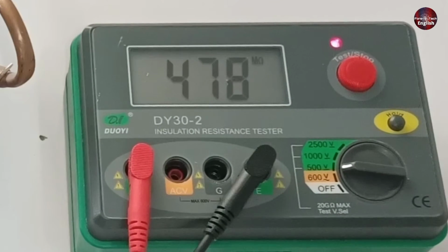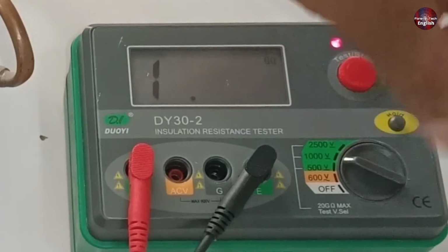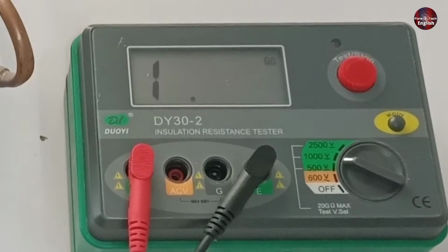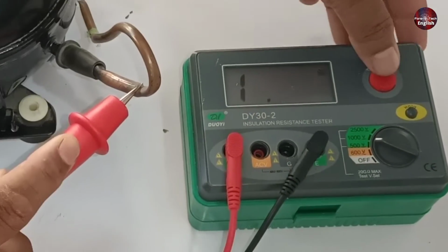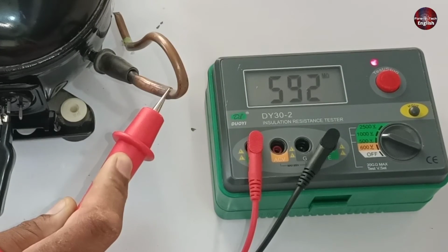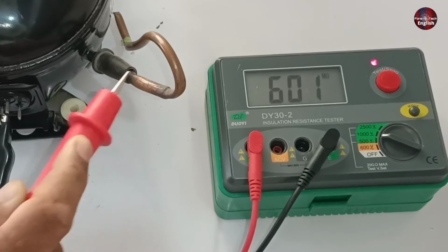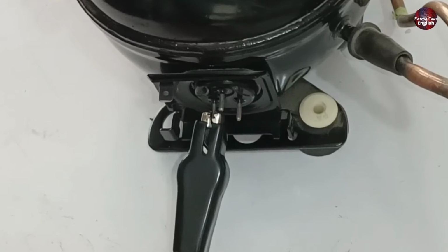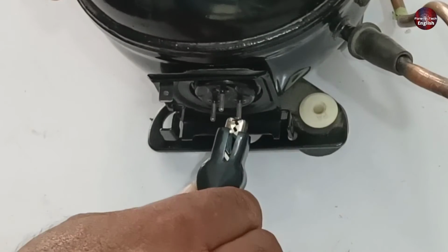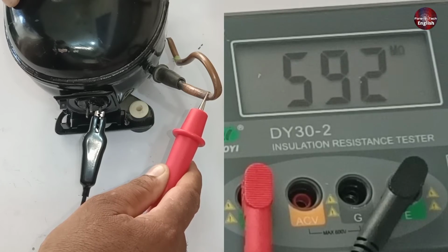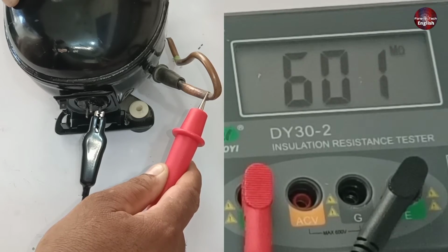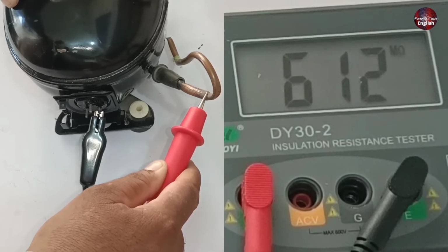It shows 570 mega ohms of resistance, which is a good resistance for the size of this compressor. Let me check what value it shows us on 1000 DC from the megger. It is increasing and going towards 600 mega ohms, which still is a good resistance. Now, let's check what resistance it shows with the next terminal. It is showing 600 mega ohms again, but the value is gradually increasing.